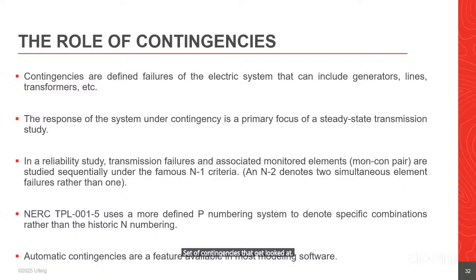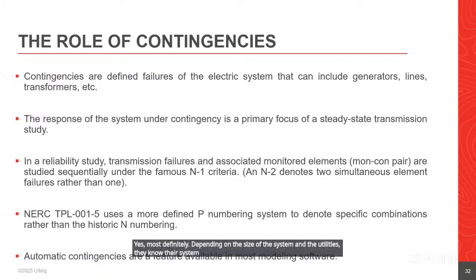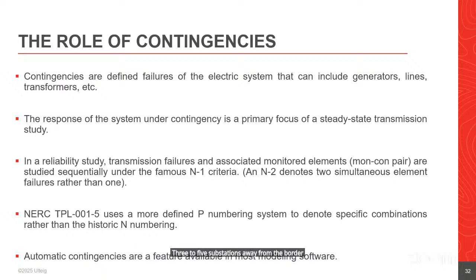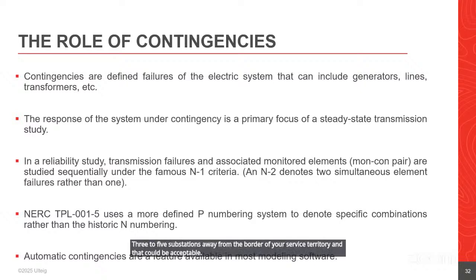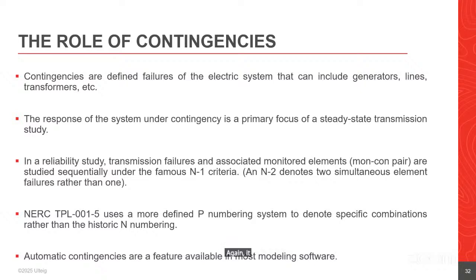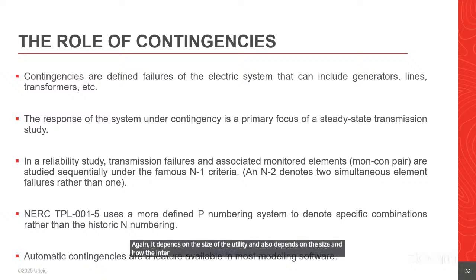Yes, most definitely. Depending on the size of the system, utilities know their system quite well. There's a file we call a monitor file that's part of what's used to run this type of transmission analysis, so you can monitor, say, 3 to 5 substations away from the border of your service territory, and that could be acceptable. It depends on the size of the utility and how the interconnection is around the utility and its neighbors.